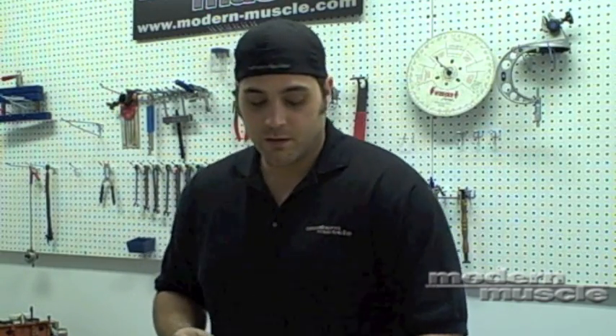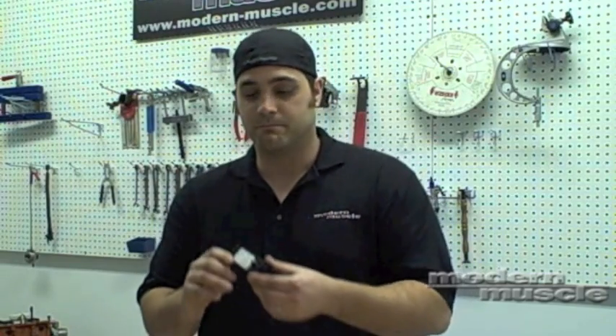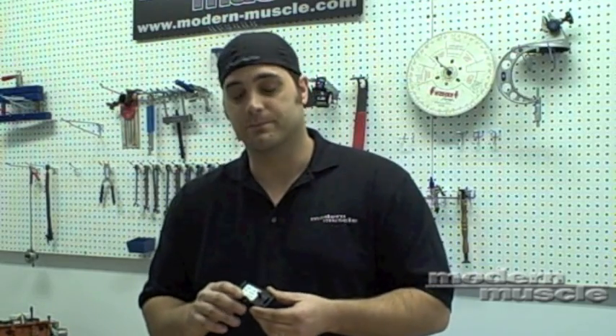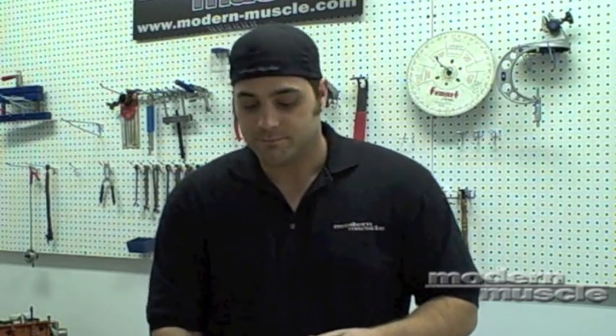That's where a closed loop control system and your O2 sensors come in. So if I've got a predicted airflow on a certain day and then it cools off, or humidity changes or the barometric pressure changes, I've got a 3 to 4% discrepancy now between my expected airflow and actual airflow.